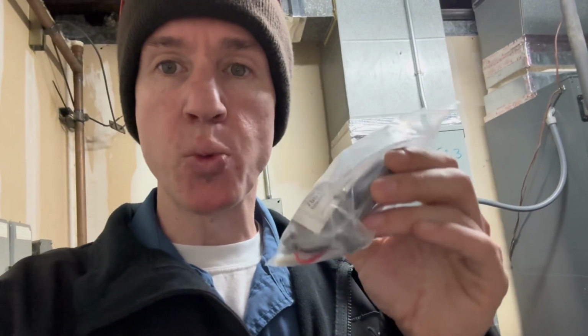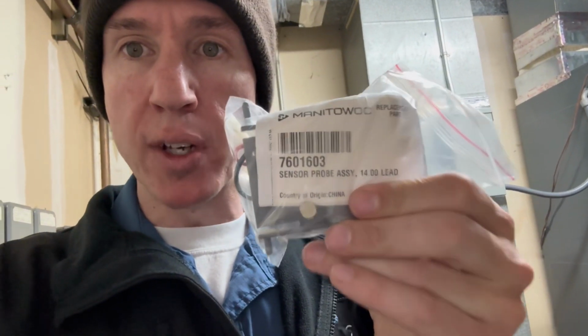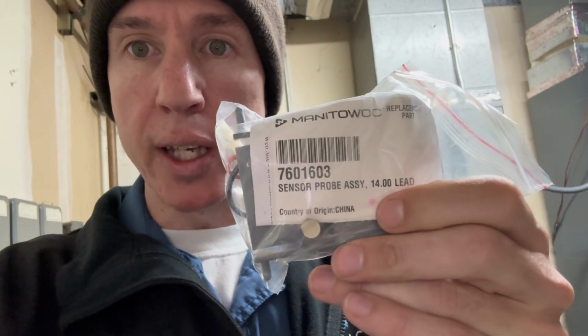And my theory is that if the ice thickness probe is sending the machine into harvest prematurely, there's no ice to actually harvest, and then the machine shuts off on long harvest. So this is what I'm going to swap out. There's the part number in case you're looking for it.